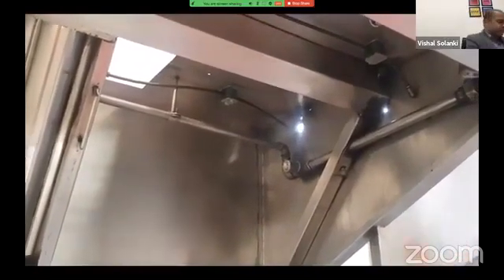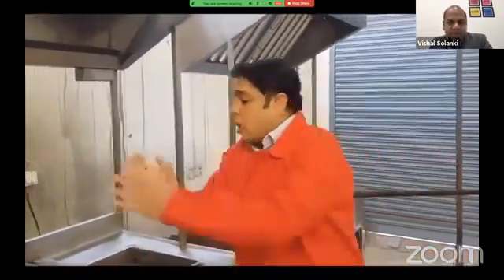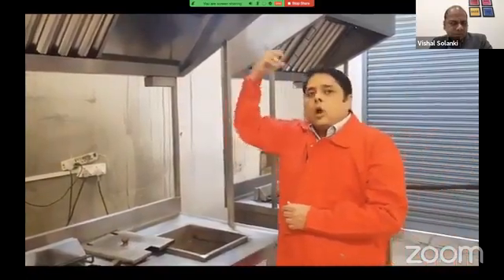As viewers, you will come in close and see. The most interesting part of the kitchen suppression system is the heat sensing tube, the HST. This black tube runs directly from the cylinder and across the plenum, covering all portions of the plenum and the duct. The HST has been designed to automatically start the system, and its continuous layout allows you to have hot and cold regions fully covered over the counters. It also covers the duct and detects fire in any flue or behind the plenum or extractor.